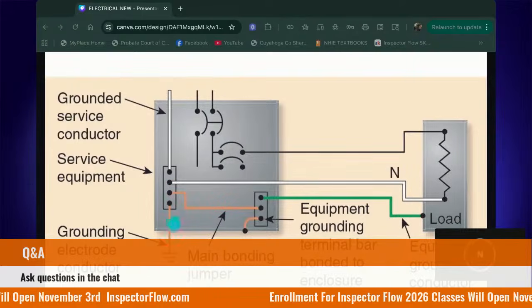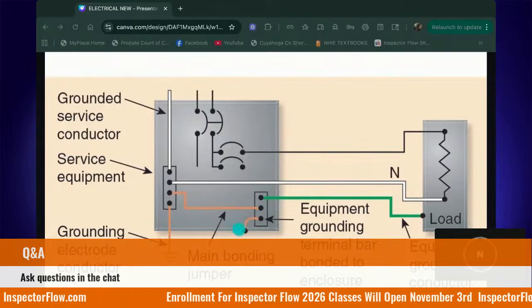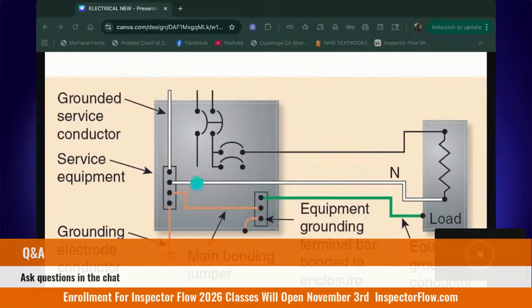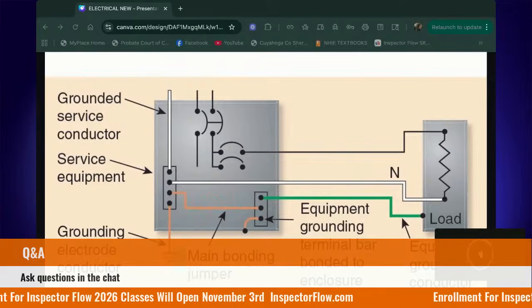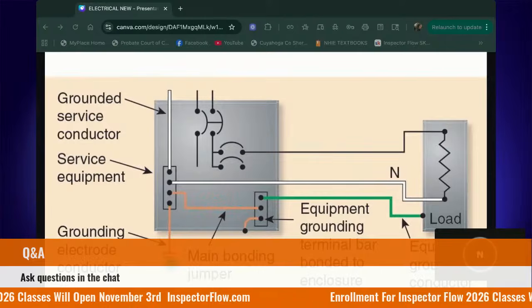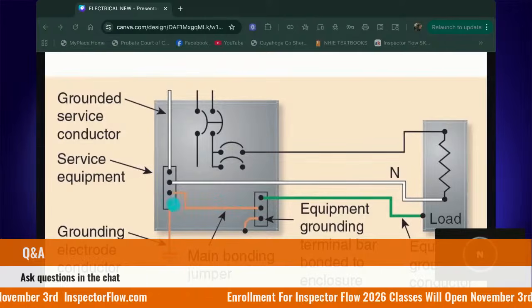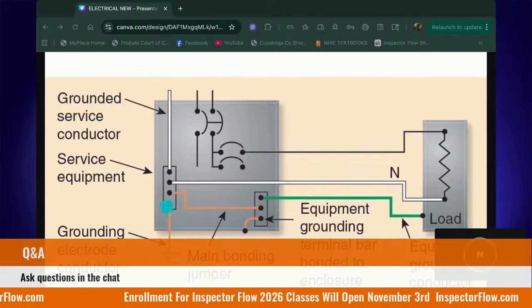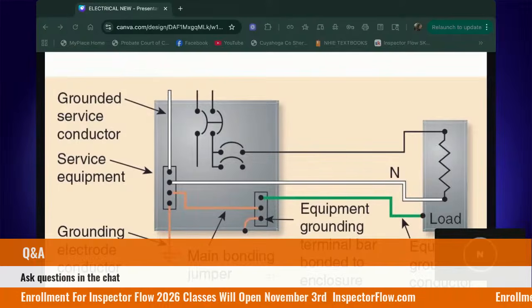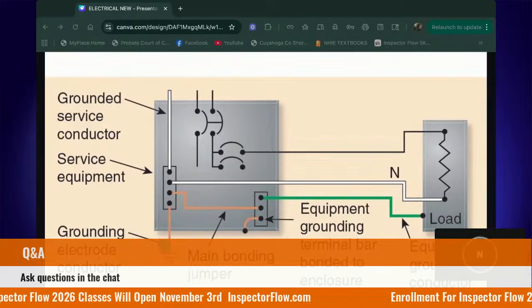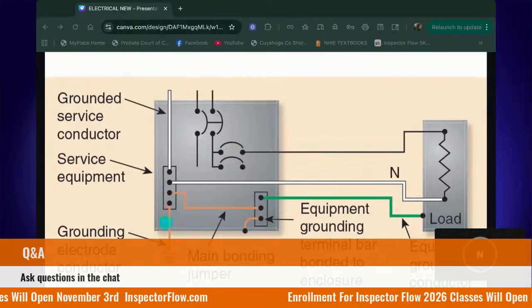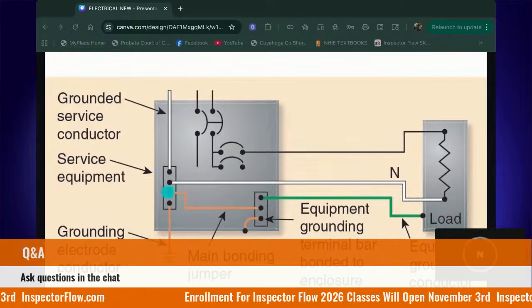Now, we have our GEC, or our grounding electrode conductor. This is the orange wire. This connects the panel's neutral bar to the grounding electrode outside. So this is where we would see that thicker copper wire. So to C's point, she said it's connected to the ground rod. Yes, but it is also terminating on my neutral bus bar.